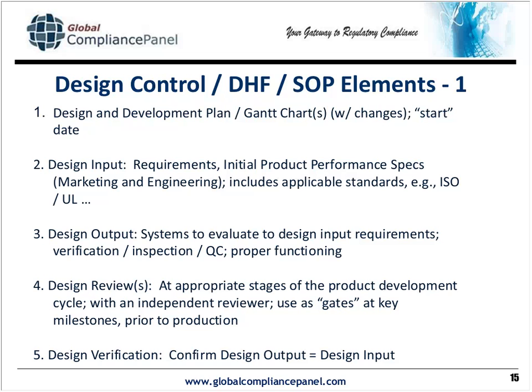Or you can put some of those under design output, but ultimately the design output would be the close to finalized documents, which would be fully finalized under design transfer. It's up to you to define how you do that. Your SOP can either spell that out or leave it a little bit vague, and as long as you include it all somewhere in those areas, and it makes sense that somebody else can follow it that's not familiar with the process that was actually done and explain it or audit it, then you're okay, providing it's in harmony with your SOP.